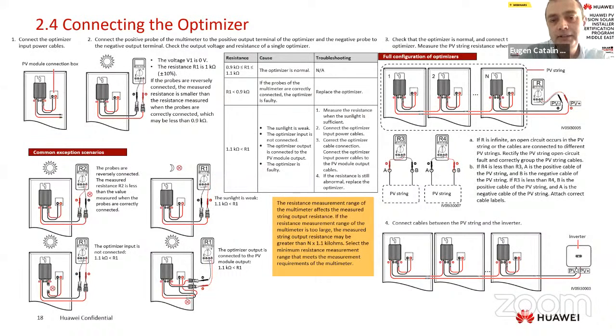Now, using the optimizer, we need to check the strings, correct? So we don't have voltage, we will have 0 volts. And as I said, we need to measure the impedance, which will be around 1 kilo ohm per panel with optimizer. We have here a table that shows what is normal and what is not normal. So between 0.9 and 1.1 kilo ohm per panel with optimizer, the value is normal. So the panel plus optimizer is good. Lower than 0.9 kilo ohm is not good: either the multimeter is not working correctly, or the optimizer is faulty. Higher than 1.1 kilo ohm is also not good.